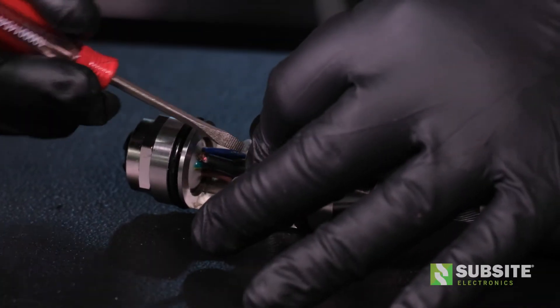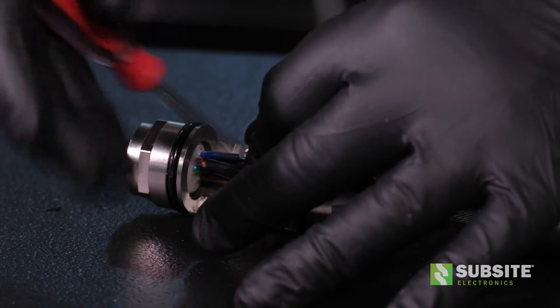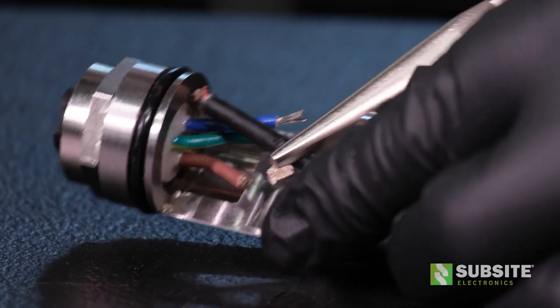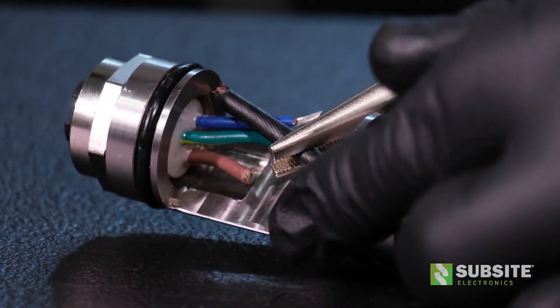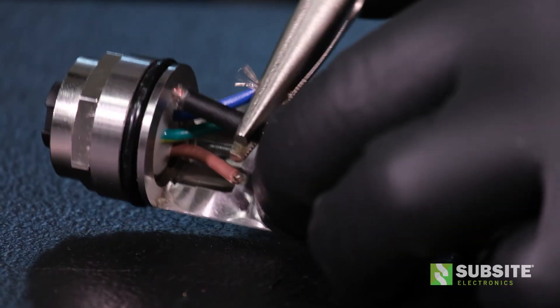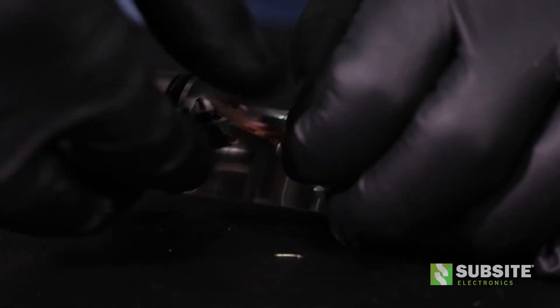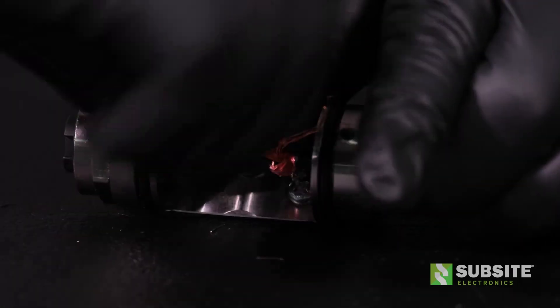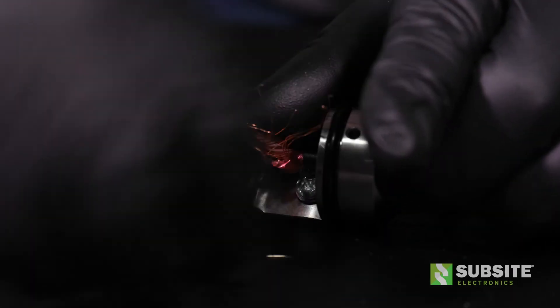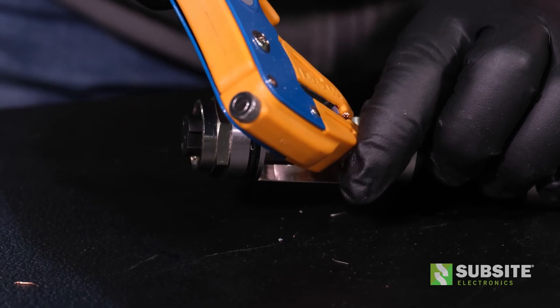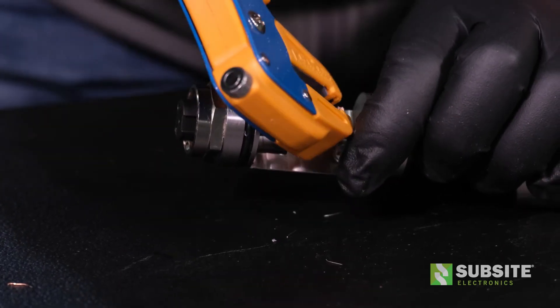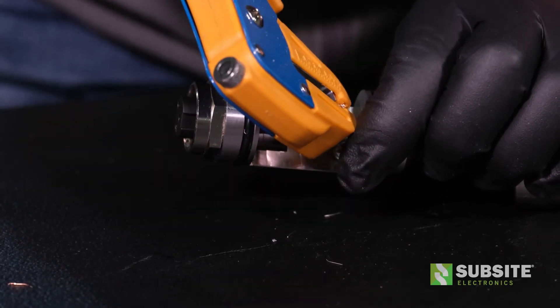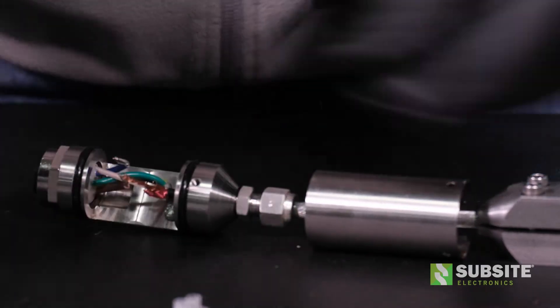Loosen the block screws to remove the terminal blocks from the bullet wires. To remove the black jacket, bend the cable at the score, then use the pliers to remove it. Separate the copper shield from the center conductor, then twist the copper shield together and trim any excess. Remove the center conductor jacket carefully using the 1.6 slot on the wire strippers. Twist the center conductor wire and trim any excess.